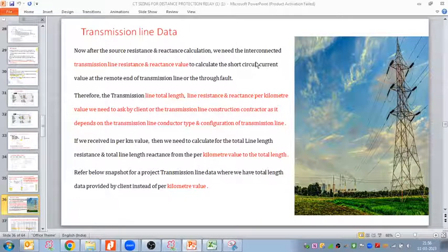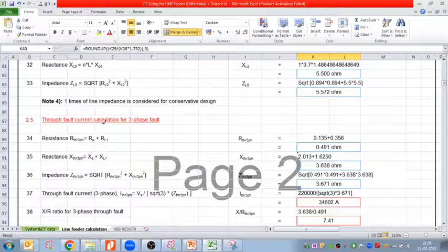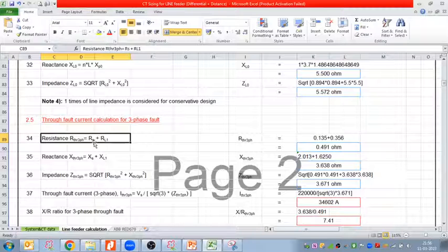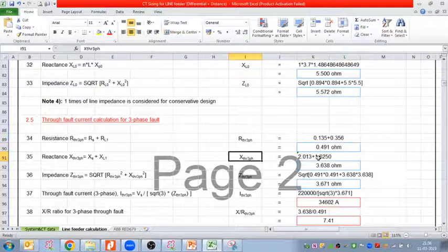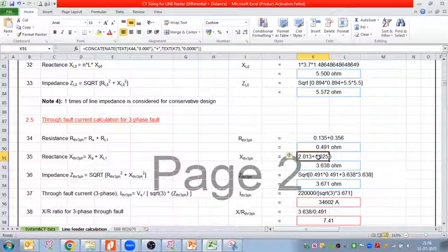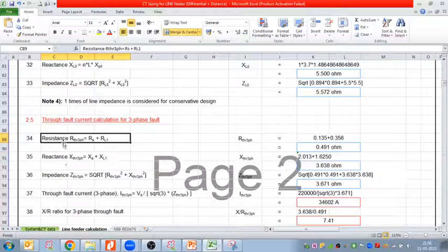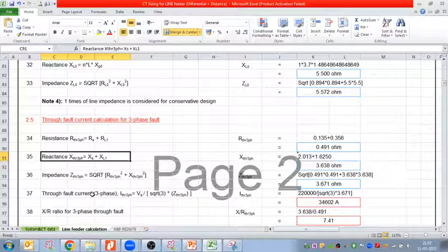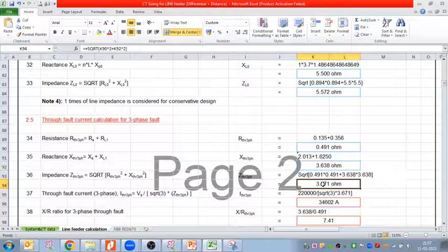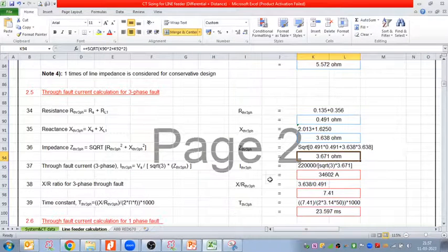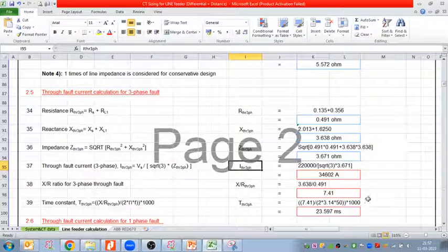Clear, Bharat? Let me tell you why we discussed the source resistance, reactance, impedance. If you refer to this through fault current calculation, the resistance till the protected point is RS, my source resistance, plus RL, my transmission line conductor resistance. We add both resistances to get the final resistance, and then we calculate the final reactance also till your transmission line last point. If the fault is happening there, that fault we are calculating now. Then we finally calculate the impedance at the fault point Z, and with the help of Z we calculate the fault current I, the three phase fault current, which comes to 34602.